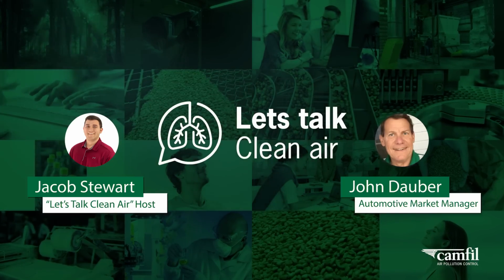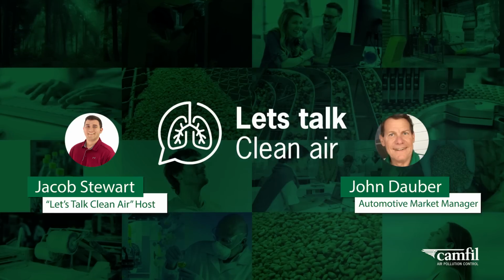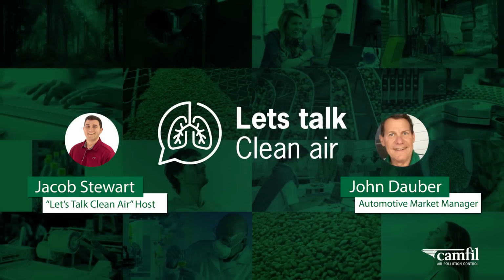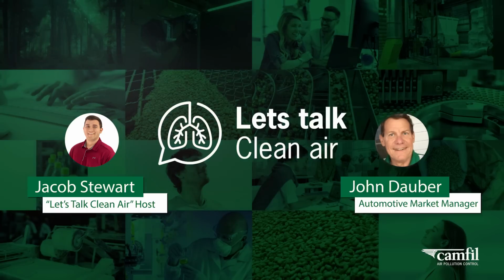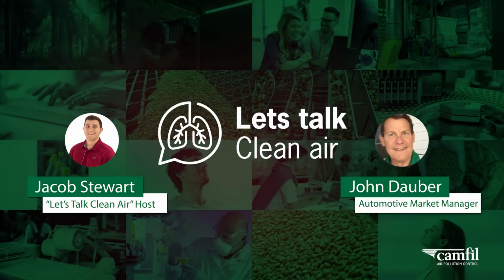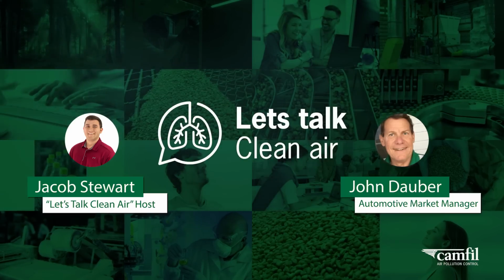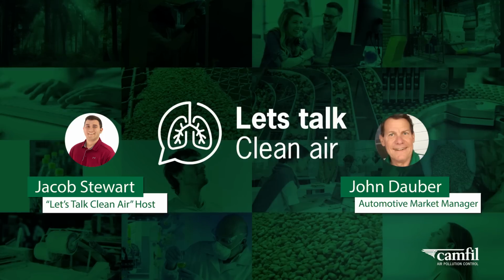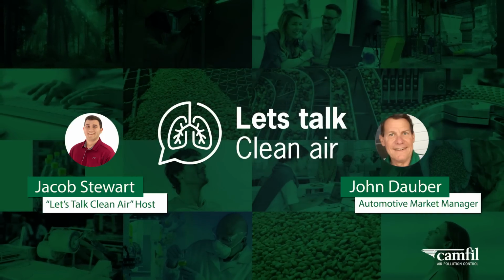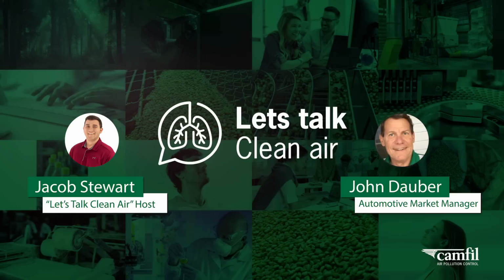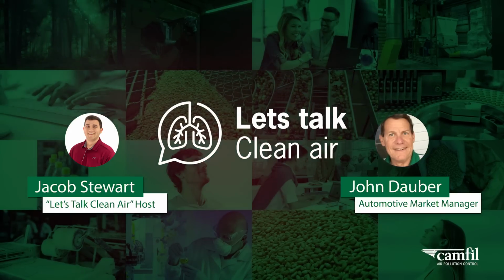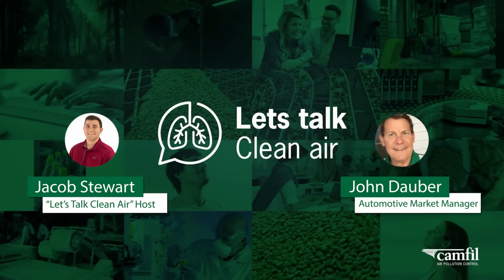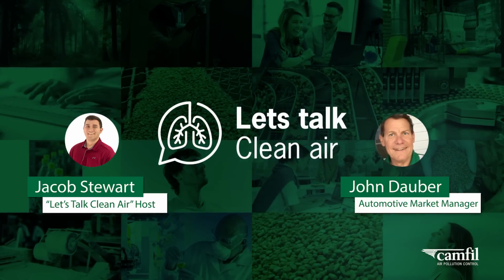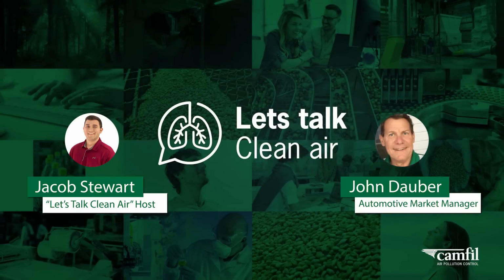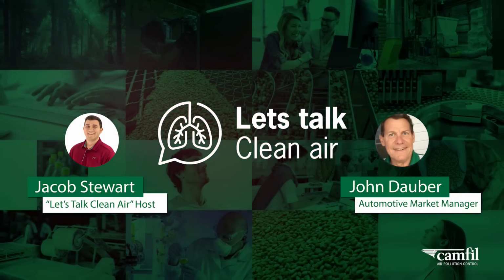Beyond that, there are independent testing labs that you should send your dust to understand, is it flammable? Does it have a KST value? And that's very important for us to recommend the correct collector and all the safety devices that need to go with it if it is explosive, if it is combustible, if it is flammable. So that's very important and actually is part of the NFPA guidelines that you do know what the hazards and risks associated with your particular dust.